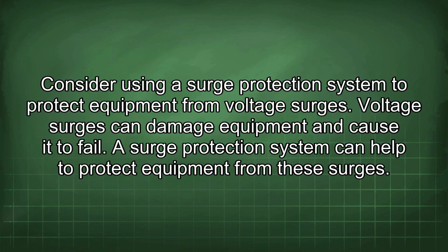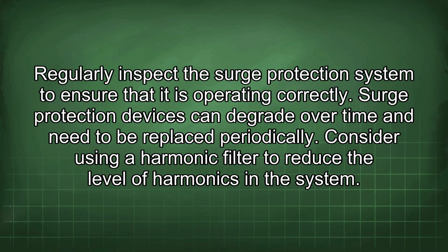Consider using a surge protection system to protect equipment from voltage surges. Voltage surges can damage equipment and cause it to fail. A surge protection system can help to protect equipment from these surges. Regularly inspect the surge protection system to ensure that it is operating correctly. Surge protection devices can degrade over time and need to be replaced periodically.